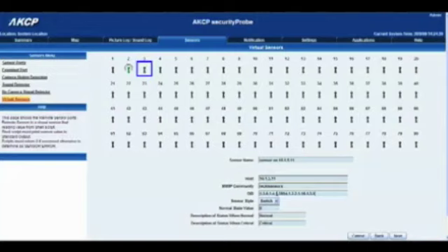Now you'll notice at the end here we have an X. Now the X is for the port number that your sensor is attached to. In this example mine is on port 1. However, with the OID, port 1 would actually show up as port 0, port 2 would show as port 1, and so on and so forth. So I'll go ahead and change that to 0, and also make sure that at the beginning of your OID you have a dot. Sensor style, we're going to switch that to analog as it's an analog sensor.